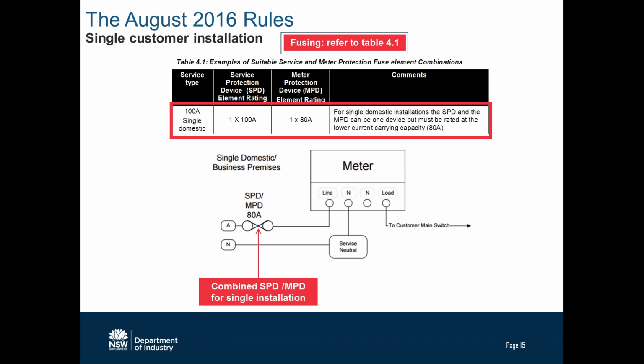For a single premises, you can have one fuse or a circuit breaker if the DNSP allows it, doing both functions. So that becomes fairly simple. All you do is replace what would have been a 100 amp fuse cartridge with an 80 amp cartridge.